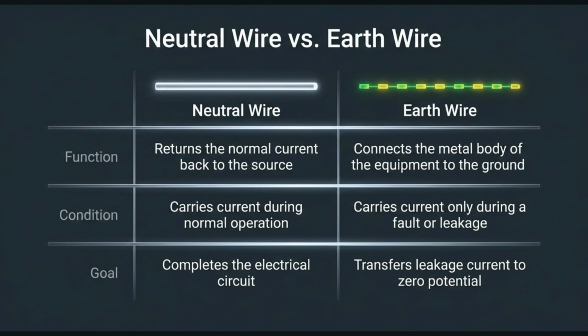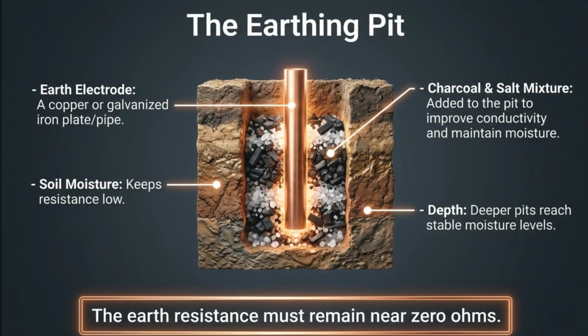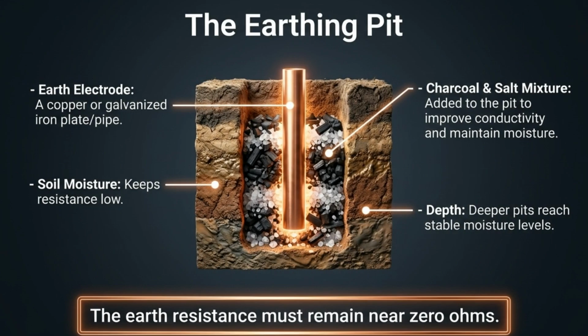The earth wire only carries current during a fault or leakage, connecting the equipment body to the ground to transfer current to zero potential. The earthing pit uses an earth electrode, charcoal, and salt mixture, relying on soil moisture and depth to keep earth resistance near 0 ohms, ensuring a safe path for leakage current.